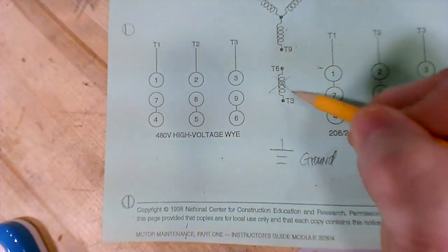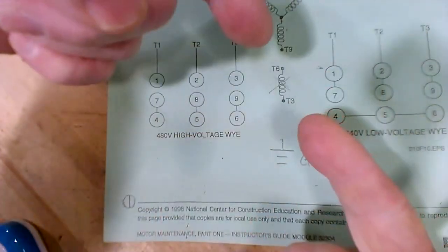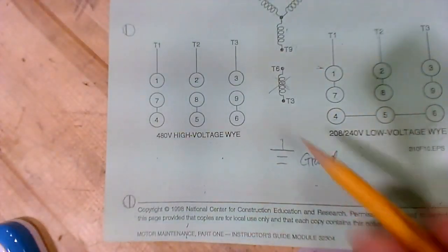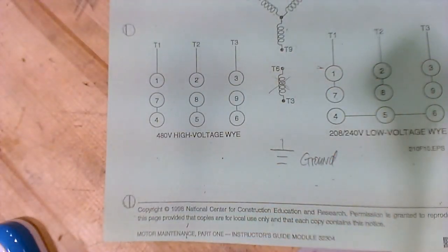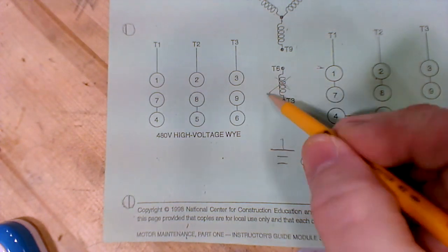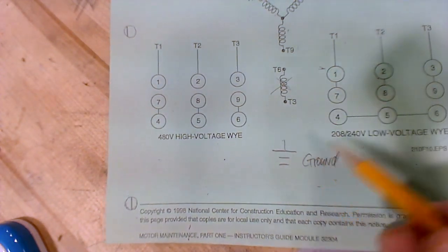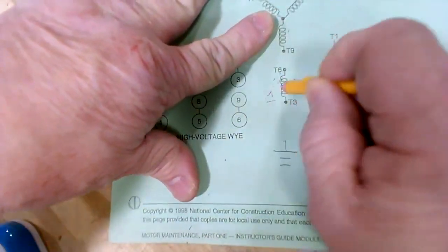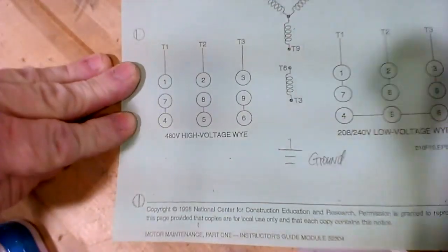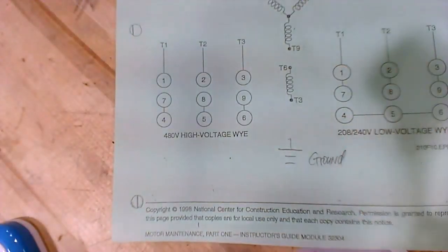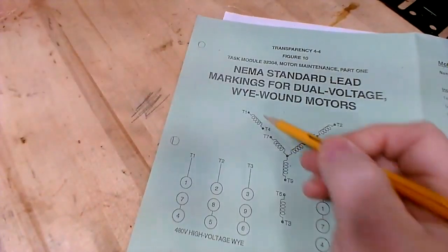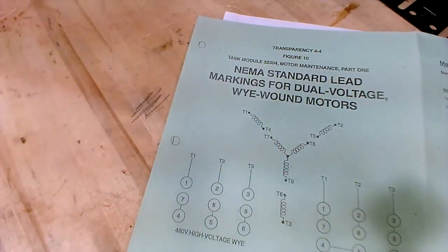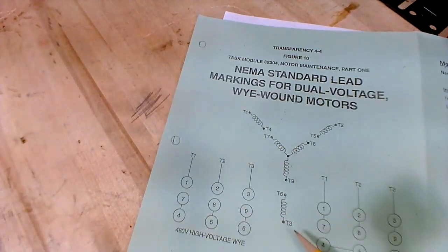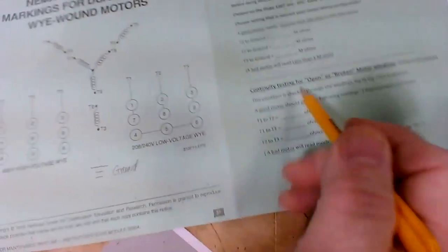So if you get one that burns in two internally, but stays free and doesn't hit the frame, then when you do a test to ground, this motor's going to read clear. It won't read to ground. But if it's got a broken winding in there, then it's going to be an open circuit, and there's a different way you have to test for that. So when you check first to see if it's shorted to ground, you're going to read with a meter from each one of these outer legs to ground with a special meter, and you're going to find out whether you have continuity to ground. If you don't, then the next test is going to be checking continuity through the winding, like this.